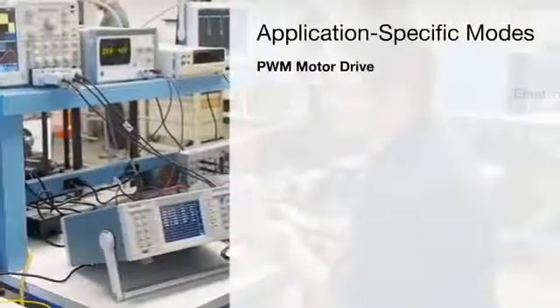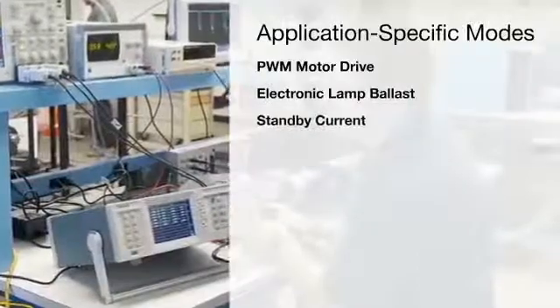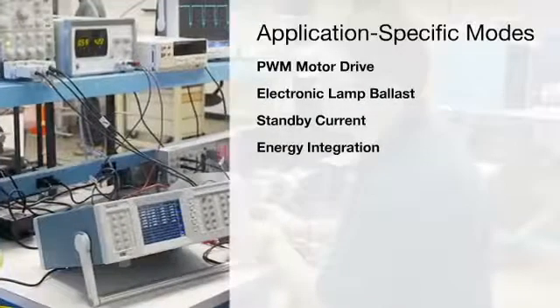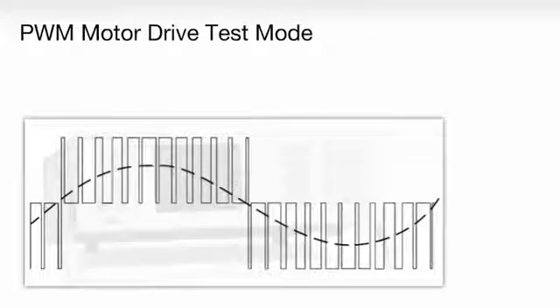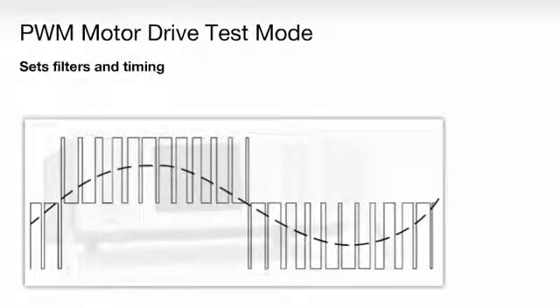Use the PA-4000's application-specific modes to automatically set filters, frequency references, and ranges for tricky modulated or wide-range signals. For example, configuring a power analyzer to measure highly modulated PWM waveforms can be frustrating. You get quick results by letting the PA-4000 take care of filter settings and timing.